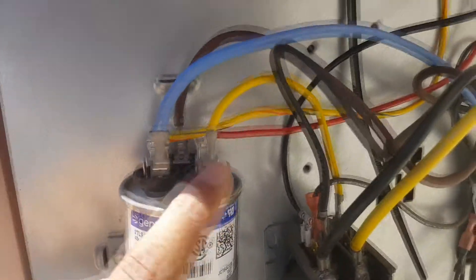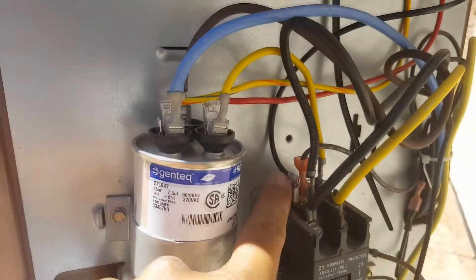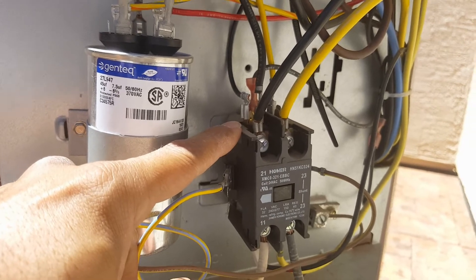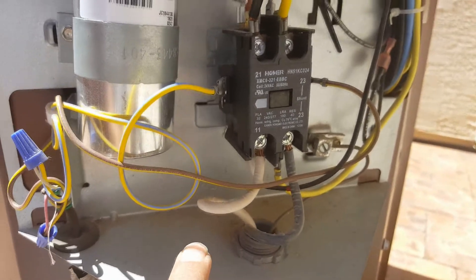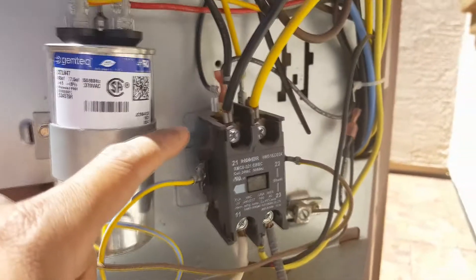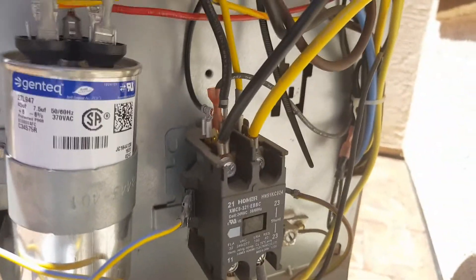The yellow wire is connected to the HERM terminal. The red wire is connected to the common terminal. The black wire is connected to the power side of the contactor — this is where the 220V leads come into the system. So you install the black wire on the black side, and that's basically it.